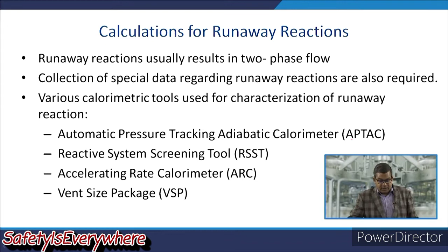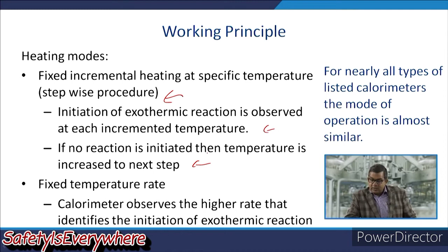Now there are several working principles involved in this sizing. Now one is the heating mode, that is the fixed incremental heating at a specified temperature, that is the stepwise procedure. So the initiation of exothermic reaction is observed at each incremented temperature. This is for the data collection. Now if no reaction is initiated, then the temperature is increased to the next step. So this is the heating mode methodology. Sometimes you may have a fixed temperature rate, so the calorimeter observes the higher rate, then identifies the initiation of exothermic reaction. So for nearly all types of listed calorimeters, the mode of operation is almost similar.